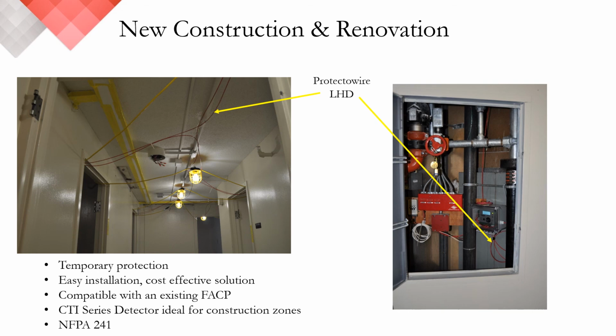This is an image of one of the more prominent colleges in the Boston area. They adopted linear heat as their primary detection method during the renovation of one of their dormitories. The detector is installed down the hallway, in and out of the rooms, providing coverage needed to safeguard the facility while the other systems have been disengaged.